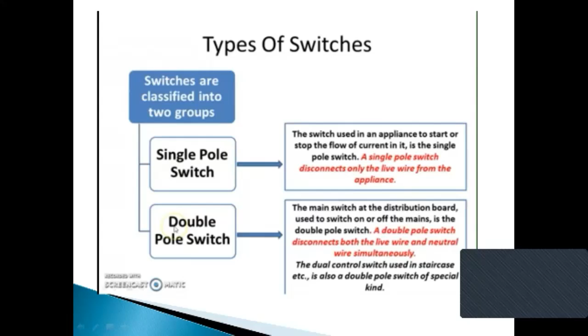A double pole switch is a main switch, called the main switch. The main switch at the distribution board is used to switch the mains on or off - it is the double pole switch. A double pole switch disconnects the live wire and neutral wire simultaneously. The dual control switch used in staircases is a special kind of double pole switch. So this is about single pole and double pole switches. Single pole switch is used with the appliances and double pole switch is used with the mains.